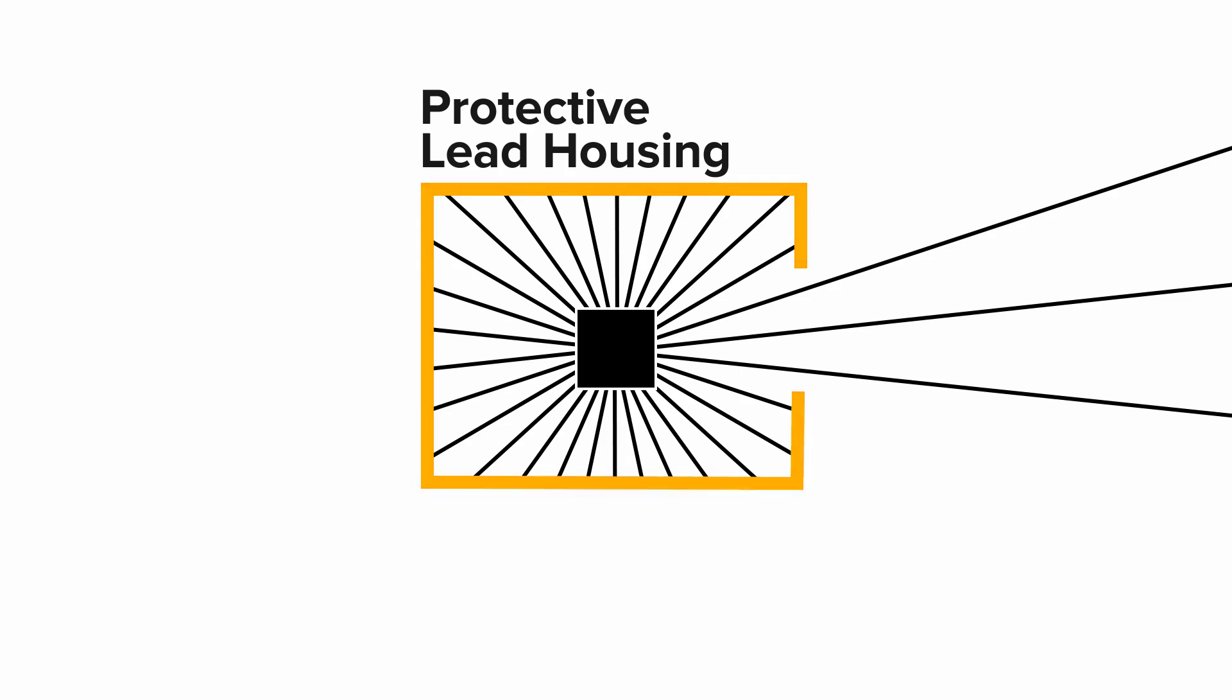The lead housing absorbs all of the extra X-ray photons that we don't actually need. X-rays travel in straight lines, so they will keep on going until we put something in the way to stop them. If they don't interact with something, they'll just keep on going. So we use the protective housing to protect the patient and other people in the room from unnecessary radiation.